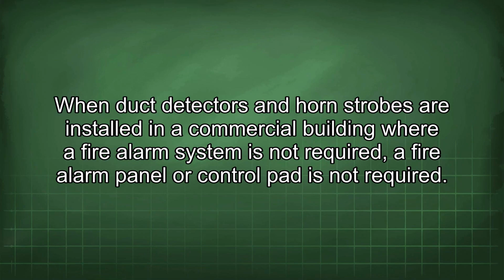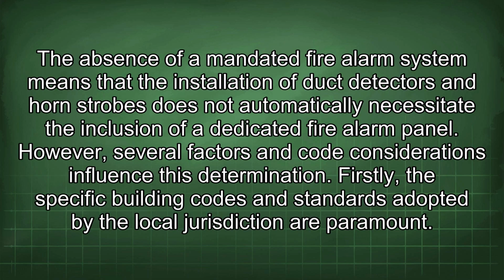When duct detectors and horn strobes are installed in a commercial building where a fire alarm system is not required, a fire alarm panel or control pad is not required. The absence of a mandated fire alarm system means that the installation of duct detectors and horn strobes does not automatically necessitate the inclusion of a dedicated fire alarm panel. However, several factors and code considerations influence this determination.